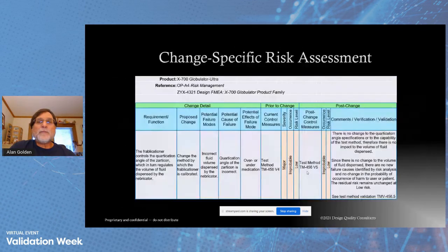All right, so I'm going to go back just for a bit. I will tell you that in my experience, we've had major changes that regulatory said we have to submit a supplement to the product's PMA before we can make the change. We actually had to get approval from the FDA. When we sent this in along with the PMA supplement, the FDA loved it because we didn't send them a 60 or 80 or more page FMEA and say, please see line 386.